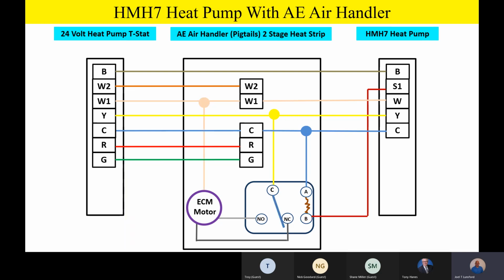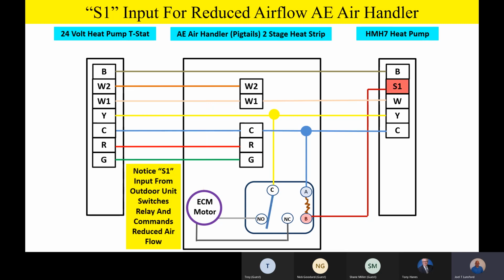Let me do that one more time. Watch the screen closely. When the outdoor unit is calling for reduced airflow, bang, it's going to generate an S1 signal. It's going to energize that relay and switch it, and then we're going to close the normally open contacts and command reduced airflow. So once the outdoor unit sees that there's a capacity reduction going on, and it starts screwing the capacity down on the outdoor unit, it'll generate an S1 signal, energize that relay, and we'll go to the lower airflow.